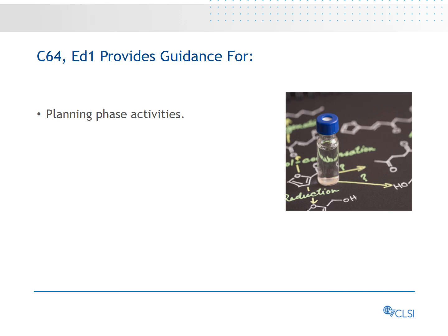During the planning phase of the project, the test developer considers the clinical utility and intended use of the test, as well as indications for the test, to assess the potential effect of an inaccurate test result and determine whether an inaccurate test result poses a safety risk to patients. Technical aspects to consider during the planning stages are instrumentation requirements for development and routine use of the test, expected timeline for method development and validation, test throughput, required turnaround time, sample preparation time, instrumental analysis time, and appropriate use of automation.